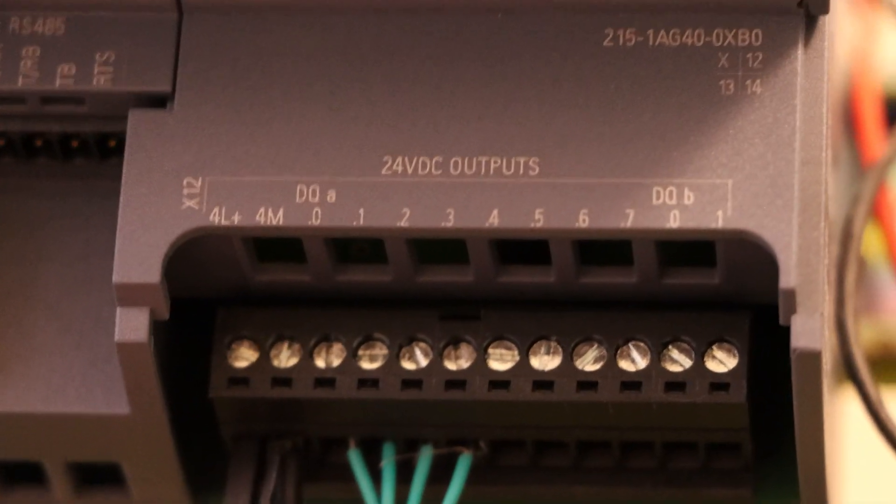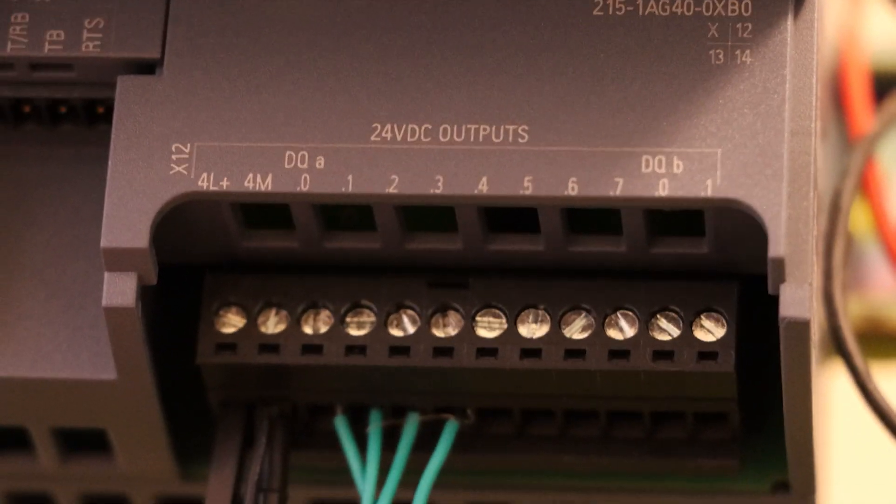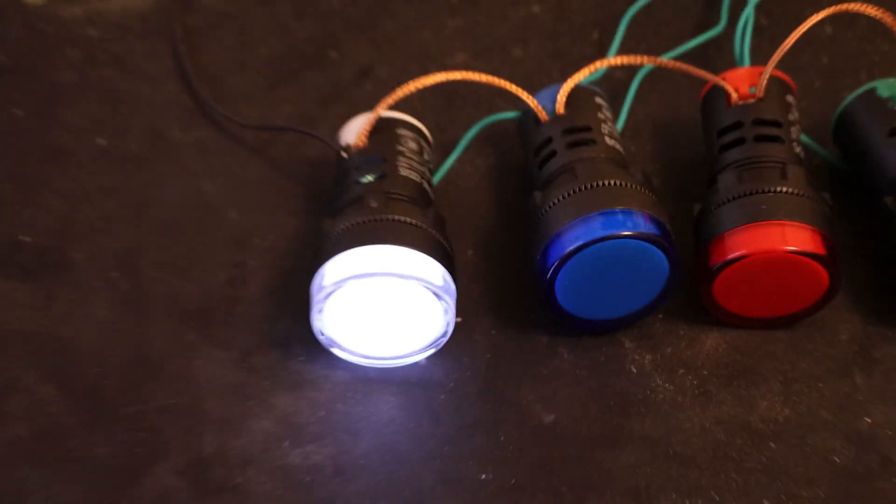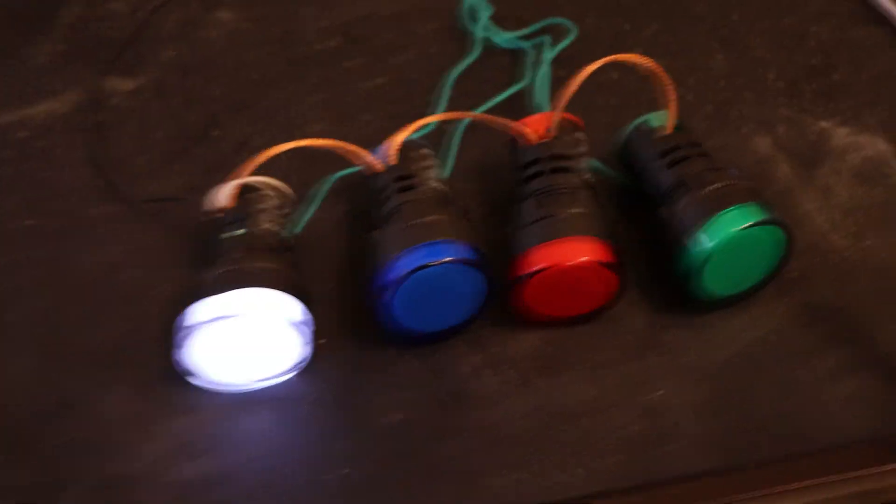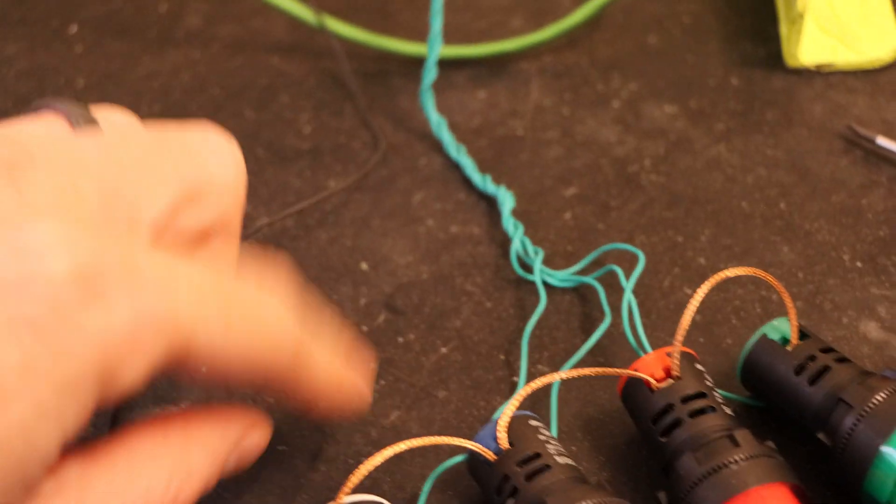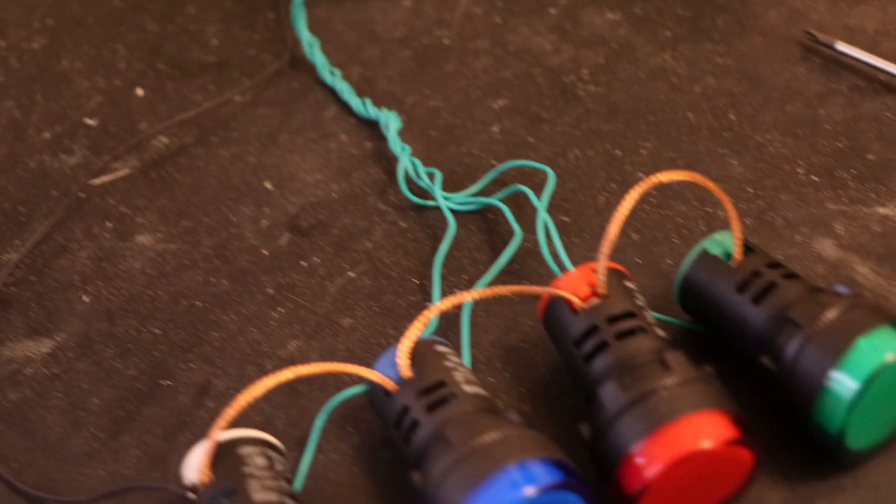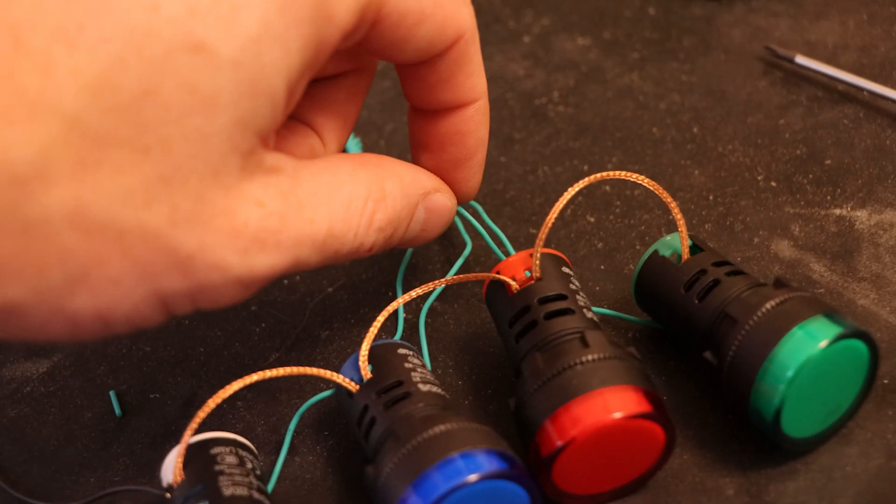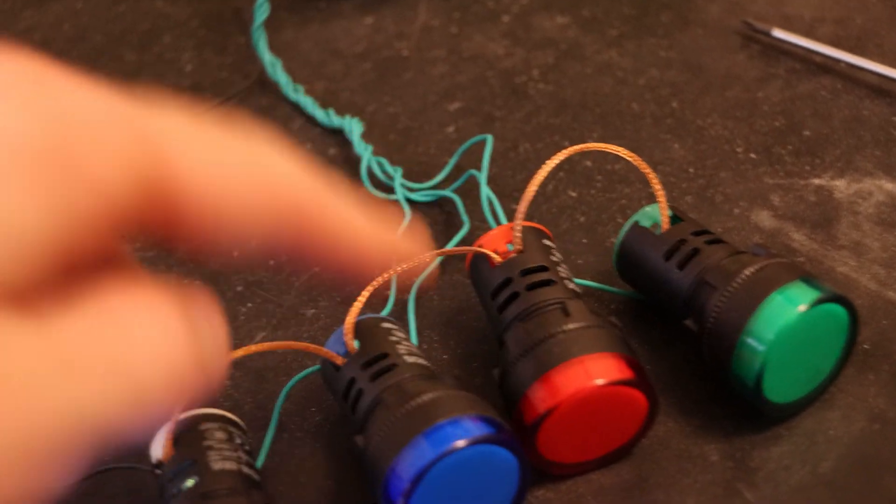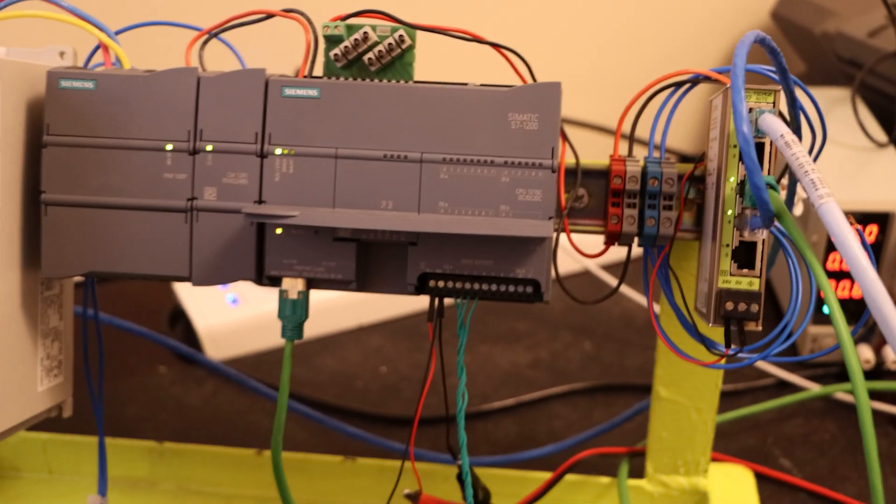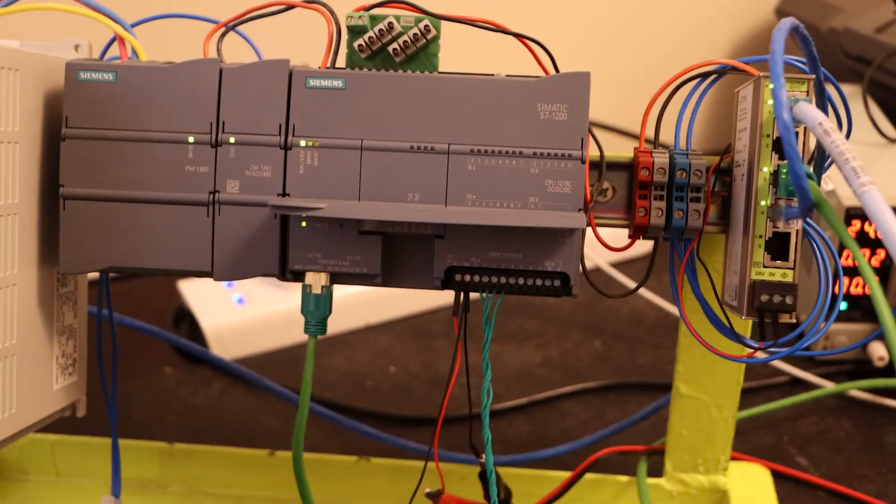So 24 volts in and common, and each of these individual green lines in the terminals - these are on our Q zero through three out to three lights. So these lights are all commoned together. This copper wire links all of the commons and that goes back up over this cable here, and the signal voltages come out to here. So when we turn one of these on, 24 volts comes down here through the light, back through the common, back to the PLC. So that is set up as what we call source.